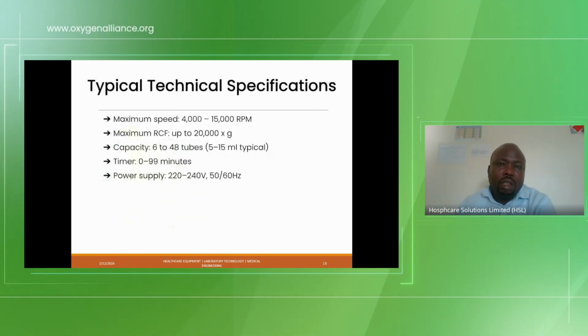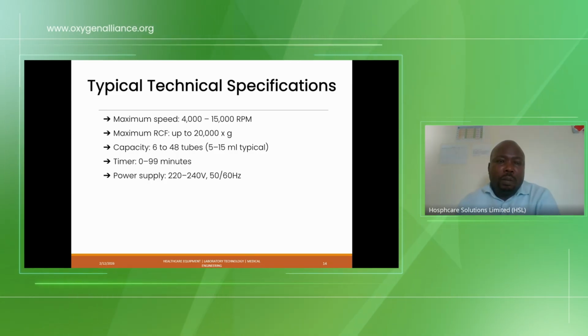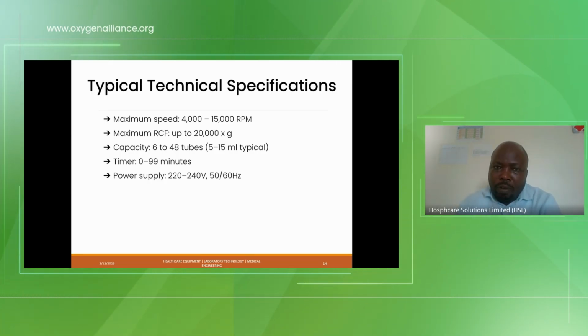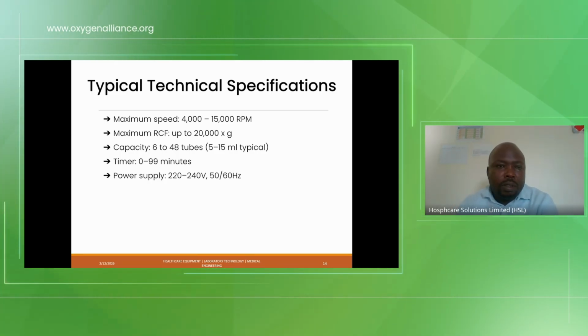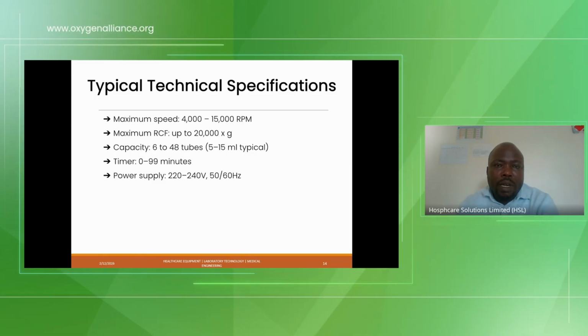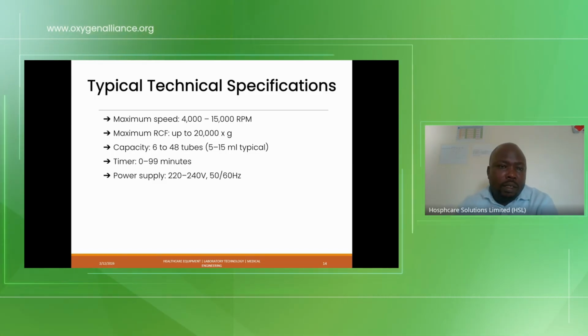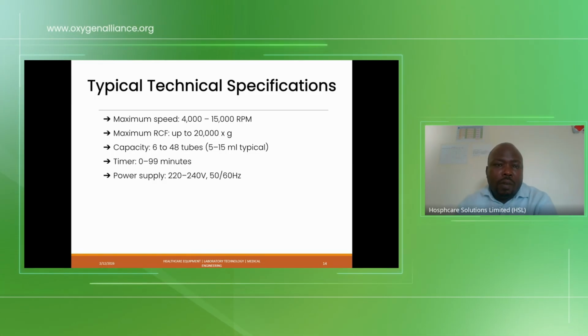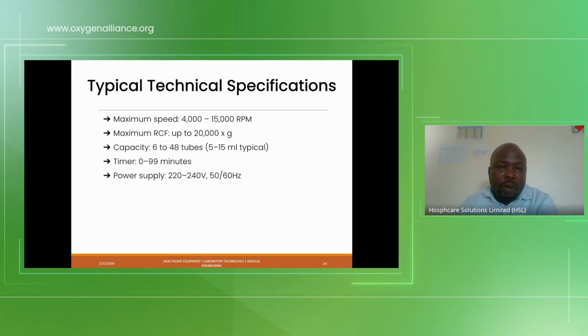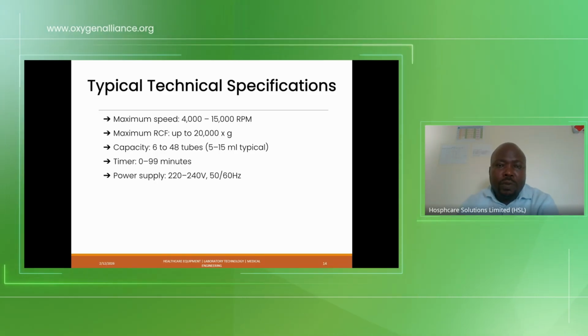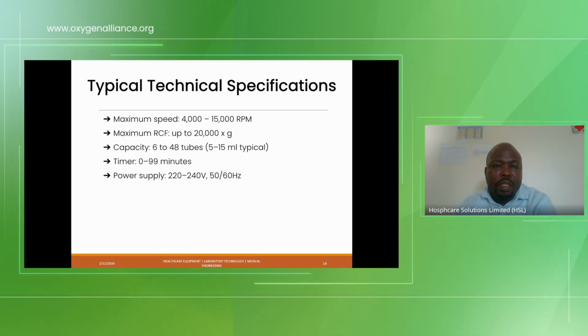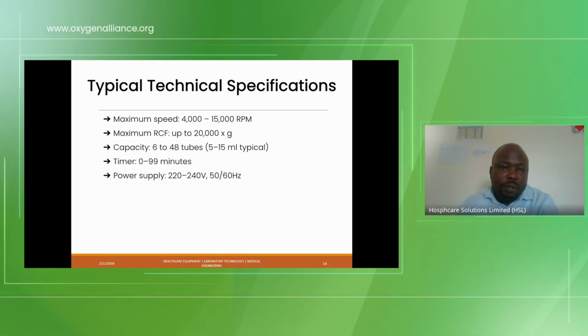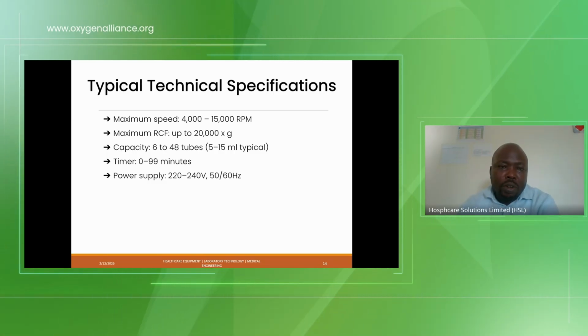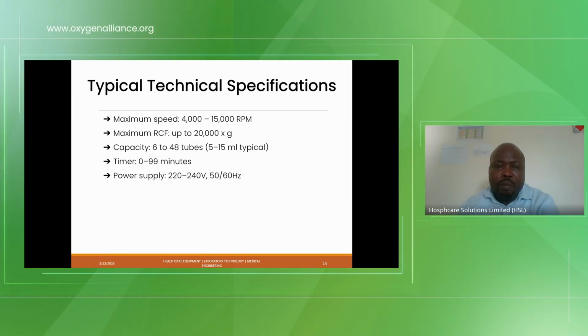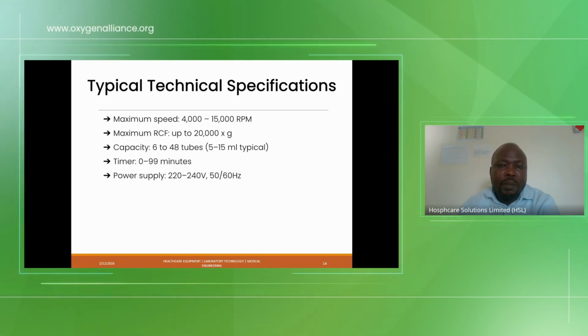separation. Typical technical specifications of a machine: you have a speed of 4,000 to 15,000 revolutions per minute, and a maximum RCF of up to 20,000 times g. We have a capacity, depending on the application, of 6 to 48 tubes. The run time can be from 0 to 99 minutes, depending on the manufacturer's specification.